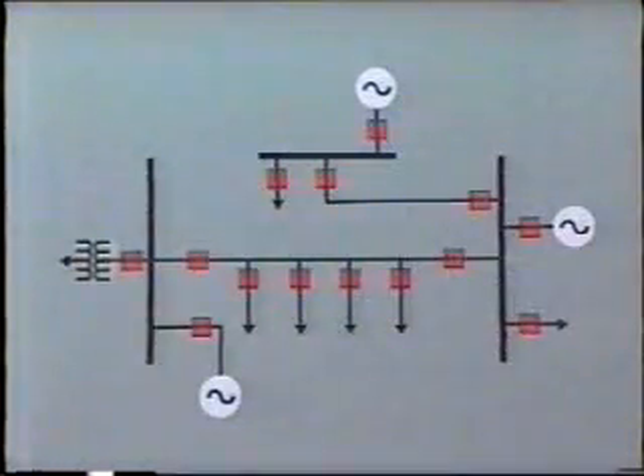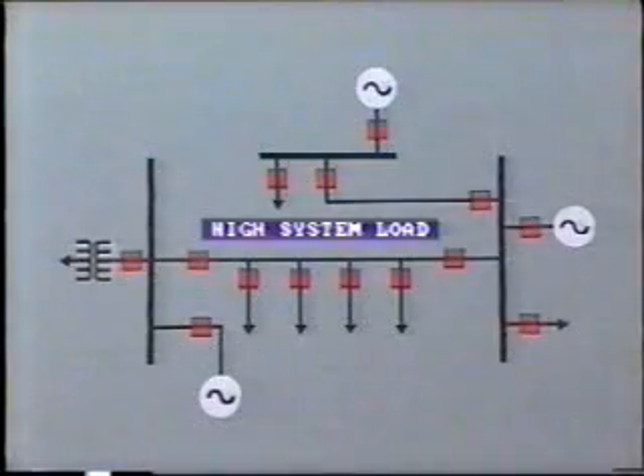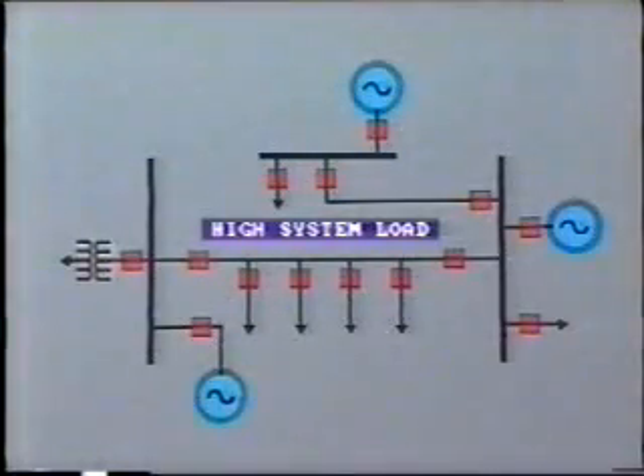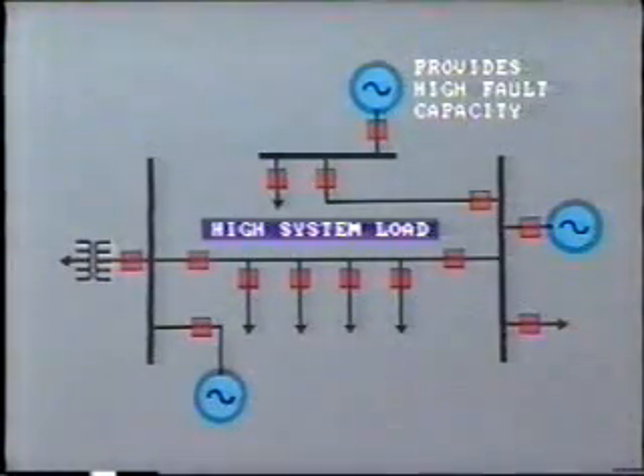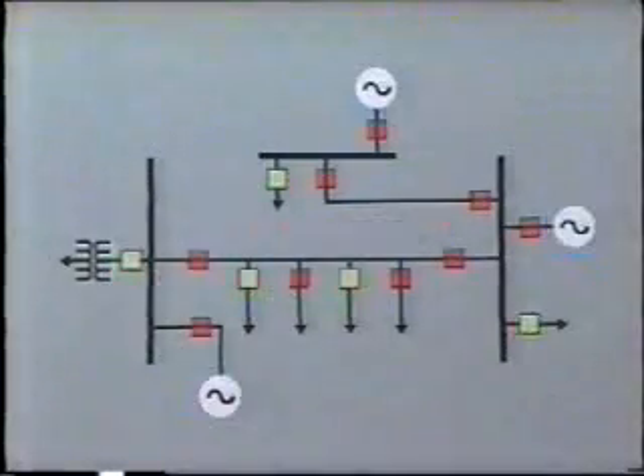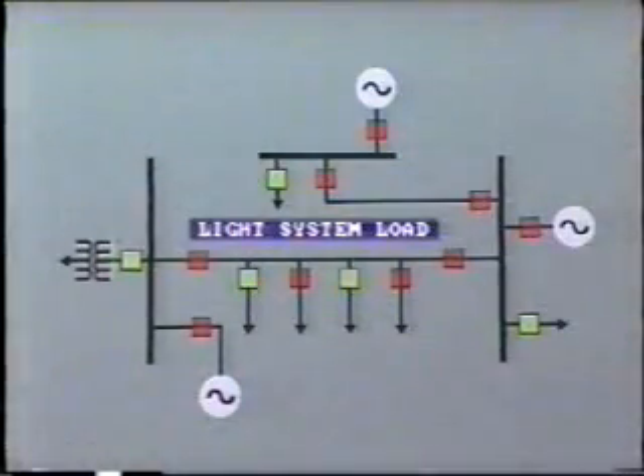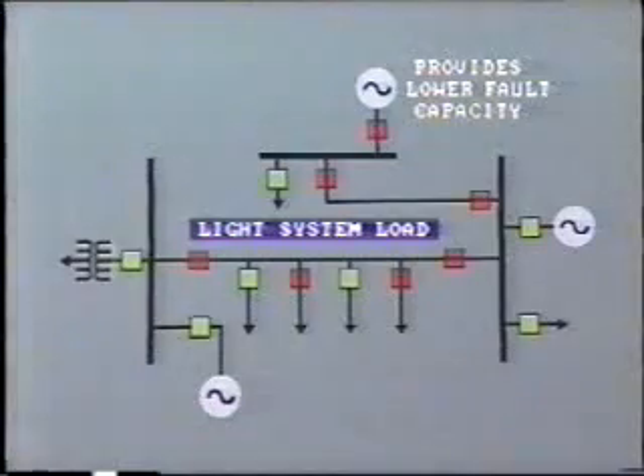There is also another factor which may affect the level of fault current, and that is the amount of fault capacity which is available at the source. What do we mean by this? Well, in periods of high load demand, we could have many generators and parallel circuits feeding into the system. This will provide high fault capacity and low impedance. Conversely, during a period of light load, some of the generators and circuits may be disconnected, so we'll have lower fault capacity. The result is that during light load, the level of fault current at any particular location may be lower than at peak time.